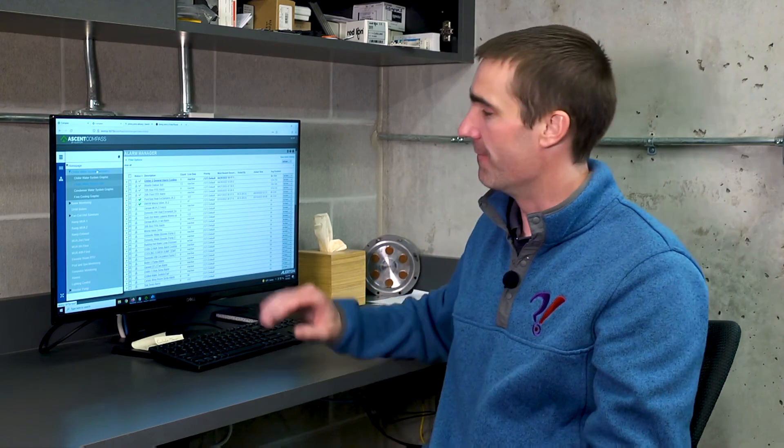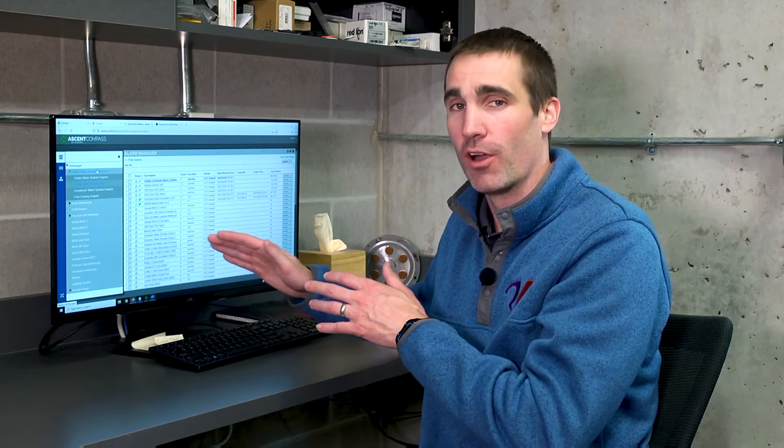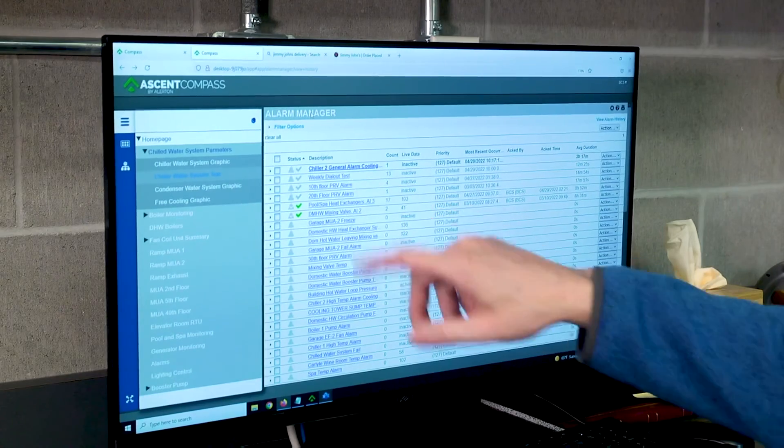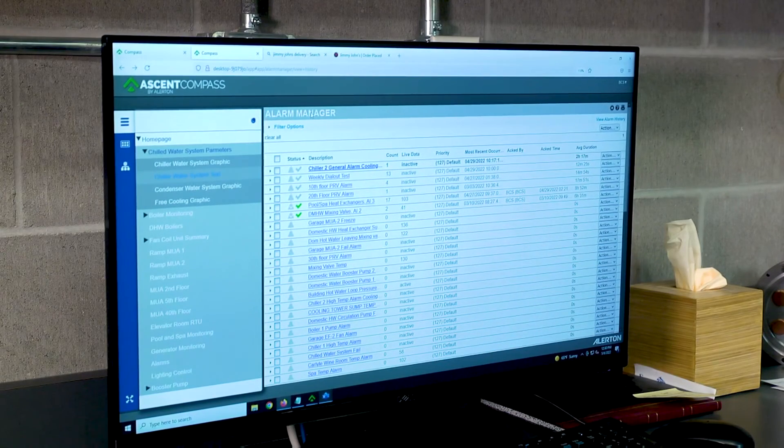A lot of times alarms come in at night or on the weekends when the building operator isn't there. It's good to investigate those, and don't just say, oh, it went into alarm. Is it still in alarm? If so, go figure out what's happening. If not, do some investigation, trend review to figure out what went wrong. Because often times you're going to find improvements that can be made, tweaks that can be made to the building automation system that can improve operational efficiency and save you energy.